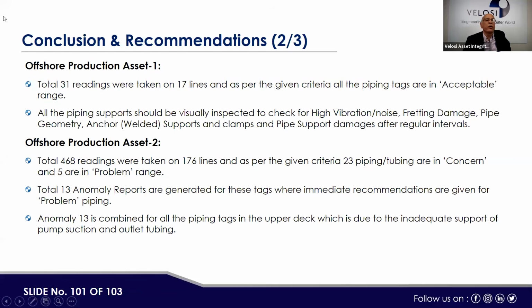And then offshore asset 1: basically, a total of 31 readings were taken on 17 lines, and as per the given criteria, all the piping tags are in acceptable range. All piping supports should be visually inspected at regular intervals to check for high vibration, noise, damaged pipe geometry, anchor supports and clamps, and pipe support damage.